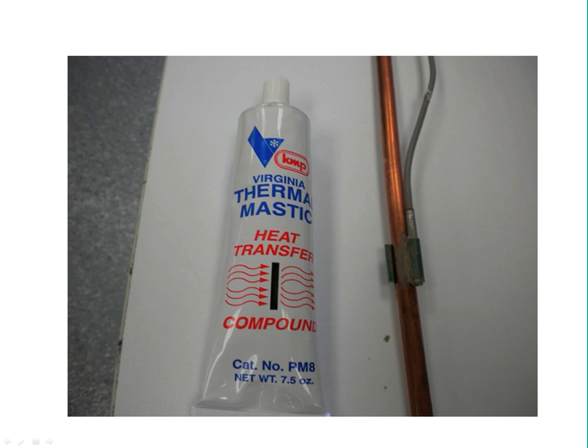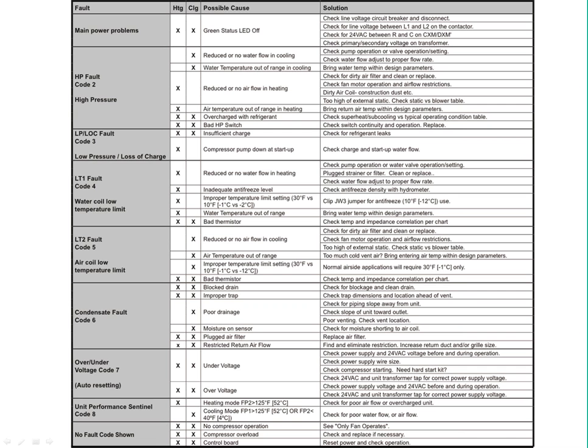So here's an example of the thermal conductive compound having been applied and then the clip attached to the copper tubing. Again, showing that we have good firm contact with that thermistor to the tubing, and we've used the heat transfer paste or the thermal conductive compound. Again, that's critically important. Again, make sure you insulate and cover that replacement thermistor, or even after you've made that test, make sure you wrap it well so it's getting good temperatures that we're trying to read, not influenced by the proximity to the compressor in the cabinet.